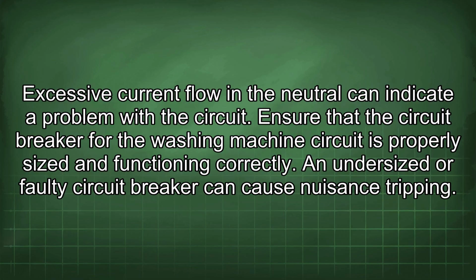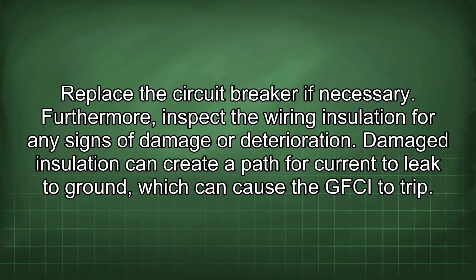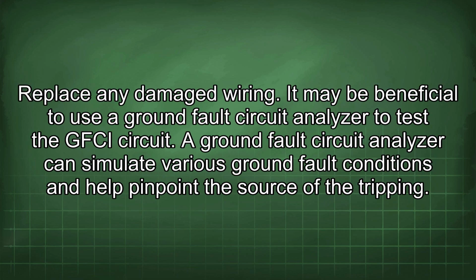Ensure that the circuit breaker for the washing machine circuit is properly sized and functioning correctly. An undersized or faulty circuit breaker can cause nuisance tripping. Replace the circuit breaker if necessary. Furthermore, inspect the wiring insulation for any signs of damage or deterioration. Damaged insulation can create a path for current to leak to ground, which can cause the GFCI to trip. Replace any damaged wiring. It may be beneficial to use a ground fault circuit analyzer to test the GFCI circuit. A ground fault circuit analyzer can simulate various ground fault conditions and help pinpoint the source of the tripping.